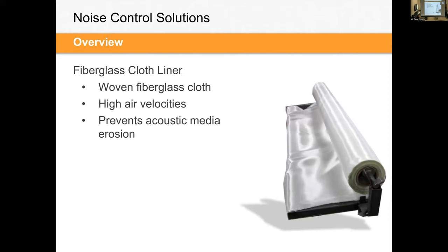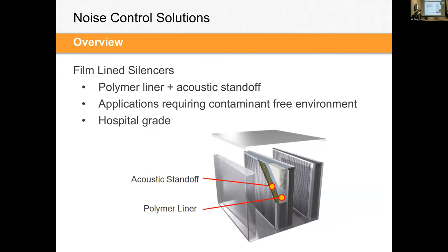One of the options we have with silencers is protecting the media. And we often use a fiberglass cloth liner. It's hard to see in the picture and get a feeling for what it looks and feels like, but it's almost like a satin feeling fabric, a very tightly woven satin fiberglass cloth. That's used when you're worried about shedding of media over time, or if you're installed right next to a fan under constant high velocity exposure, it can help protect that media.